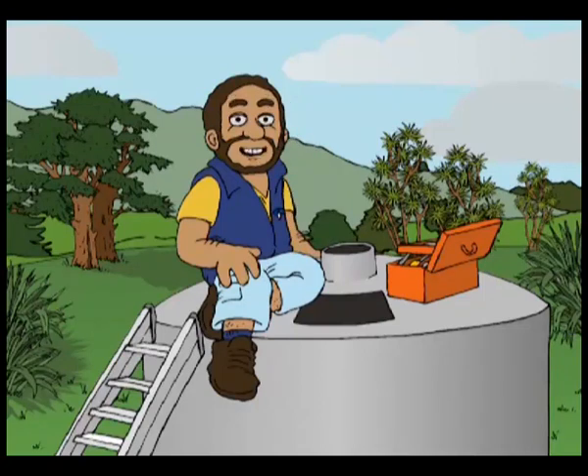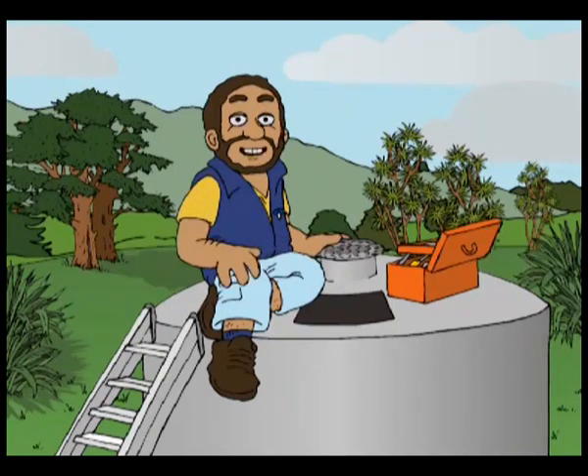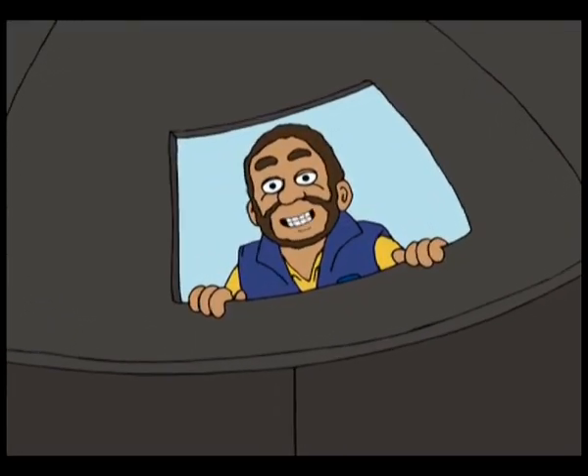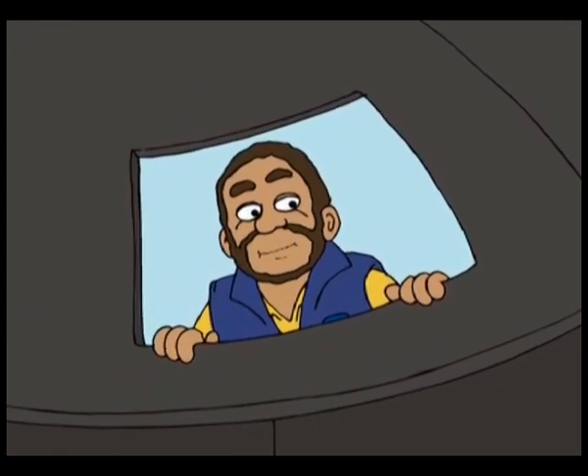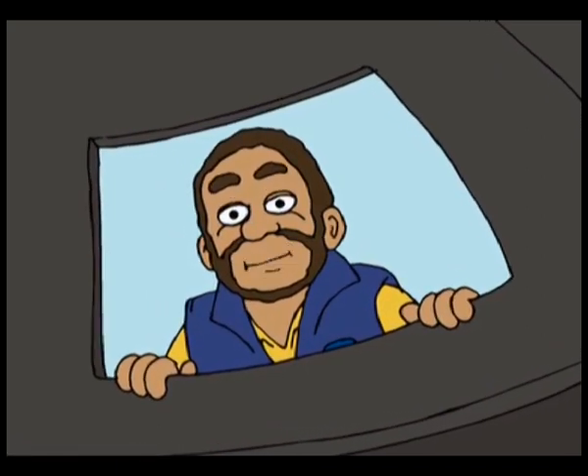Tank vents are a necessary part of the system. They must be covered or screened by a mesh screen. Secure hatches and non-corrosive screens are needed to prevent small animals or birds from entering and recontaminating the water. Overflow pipes also need to be protected from entry by birds and animals. To ensure the reticulation system remains secure, it needs to be regularly maintained. This could include inspections of tank hatches, vents and overflows, and periodic microbiological tests to confirm recontamination hasn't occurred.